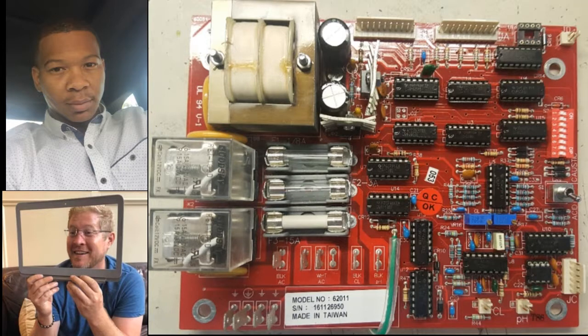Yeah, and so those are what's going to adjust the set point as the screw is turned, and then on the red board, you're going to end up with a 20 millivolt leeway per notch, right? And the blue board is 40. Each notch on the ORP, blue board, is 40 millivolts on the ORP side. Like I said before, pH is the same for both circuit boards. Right, pH is the same.